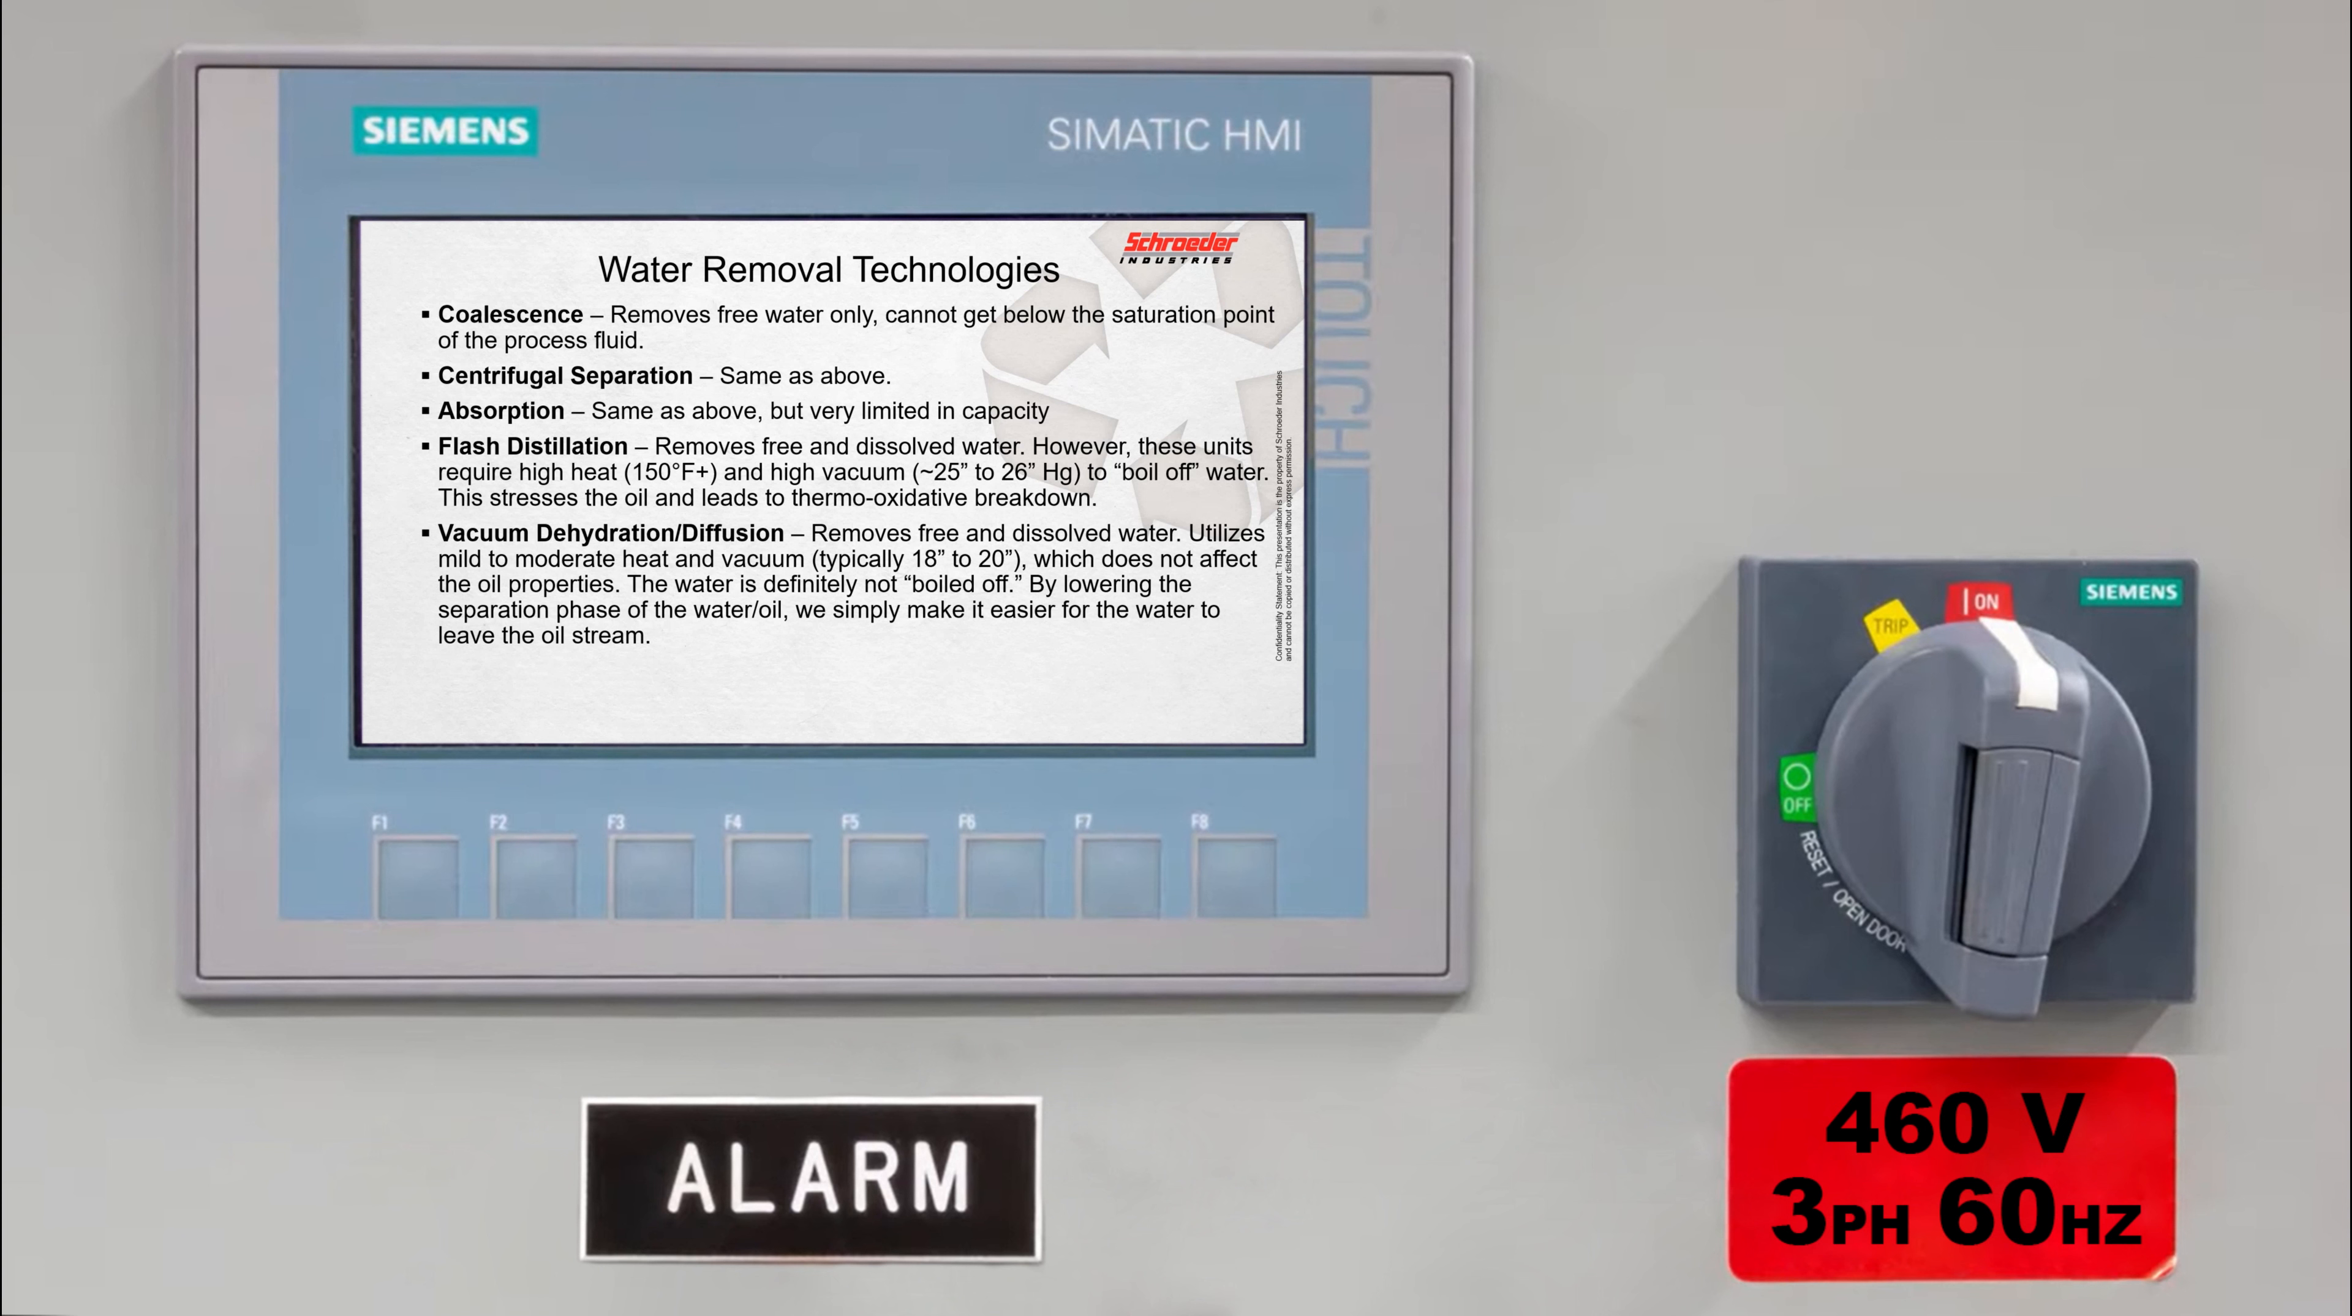What we use on our NAV is a mass diffusion type dehydrator. We'll remove free and dissolved water, but we're going to do it with moderate heat and a much lower vacuum, typically around 18 to 20 inches of vacuum. We only really need 125 degrees of temperature. It gets a little faster at water removal up to 140, but that's really all the temperature that we need to do it. We're basically lowering the separation phase of the water in the oil and we'll pull it out that way.